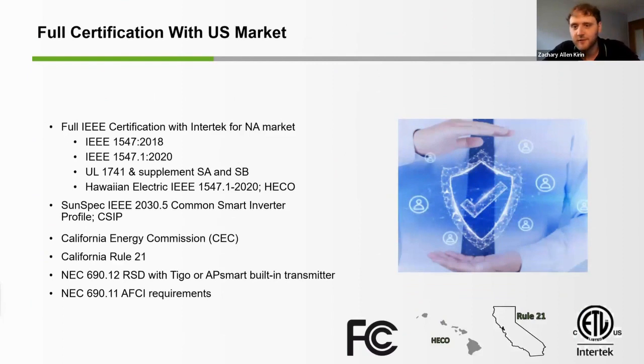The MIN TL XH inverter is fully certified with the North American market. The MIN has been certified with Intertek for IEEE 1547-2018 and IEEE 1547.1 2020 for the Hawaiian Electric grid. We are certified in both supplements of the UL 1741 standard, SA and SB. We are also compliant with Rule 21 of California, NEC 690.11, the AFCI requirements, and NEC 690.12, rapid shutdown compliance.